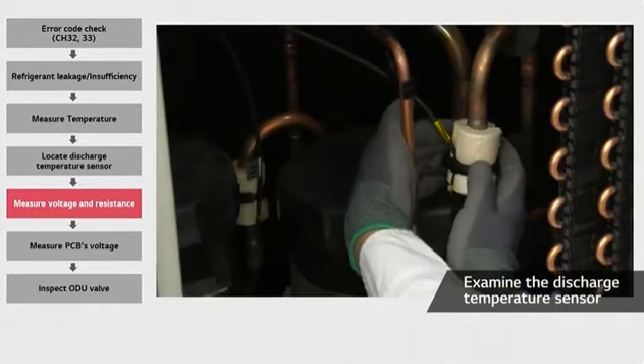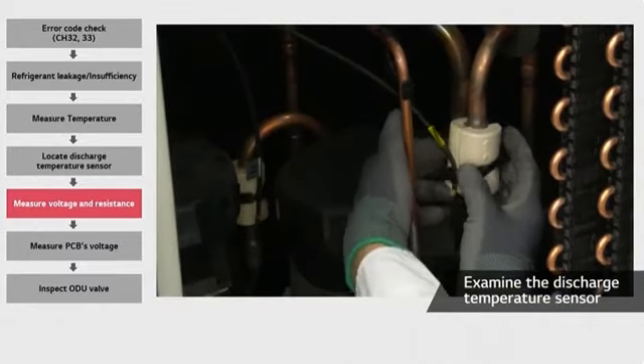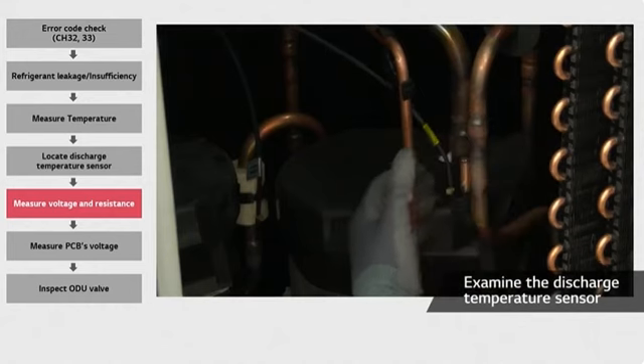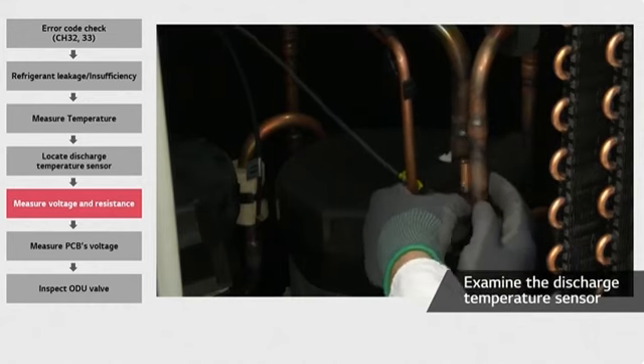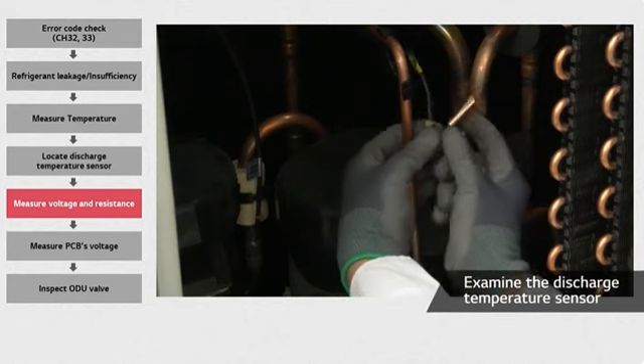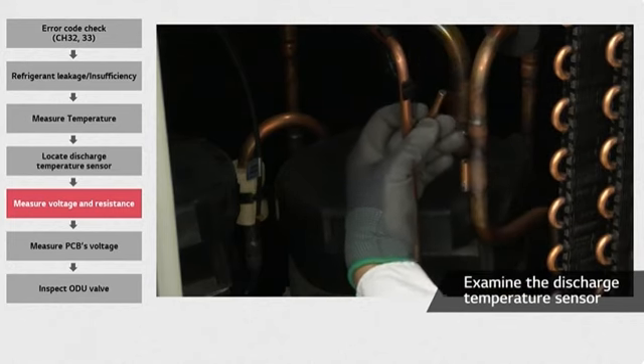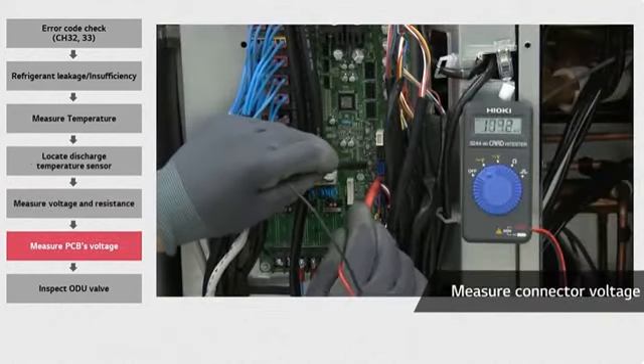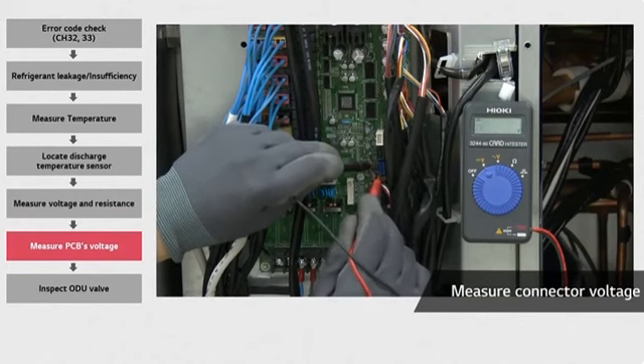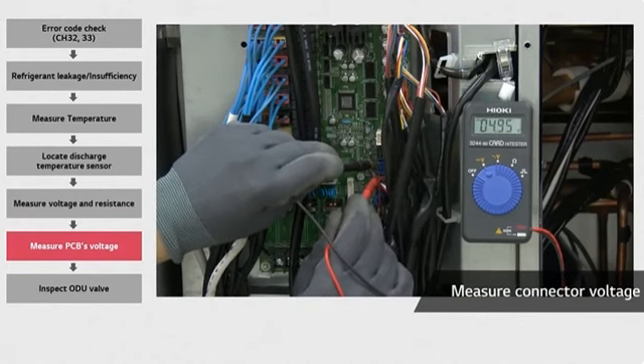If you find any problem with the discharge temperature sensor, replace the broken sensor. To remove the broken sensor, unfasten the clip, remove the insulators, and pull them out. Make sure the DC voltage from the external PCB, the blue connector, is 5 volts.